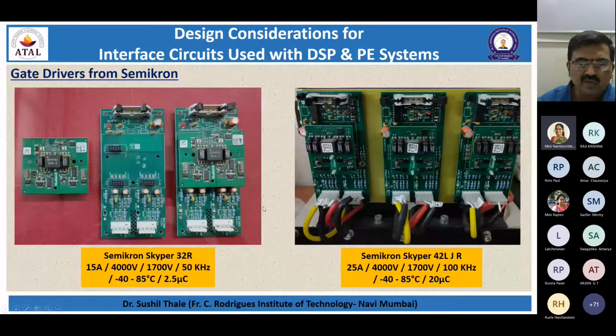These are very standard. Why did I show this picture? Because these are very commonly seen in most research labs, easily available off the shelf from vendors locally, and roughly cost around 1700 rupees a piece for the Skyper 32R, plus roughly 500 to 600 rupees for the base board. So 2000 rupees plus is the cost of each one, and each one can drive two switches, that is one leg module straight away. This capacity of 25 ampere, 15 ampere, 1200 volt DC link voltage, 50 kilohertz, 100 kilohertz should be taken into account while selecting this.